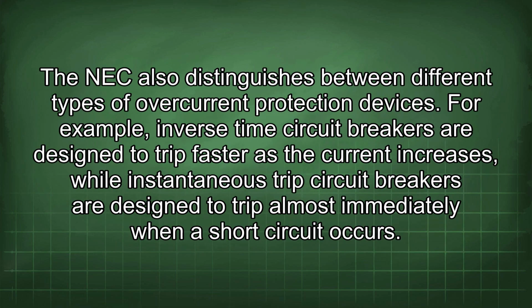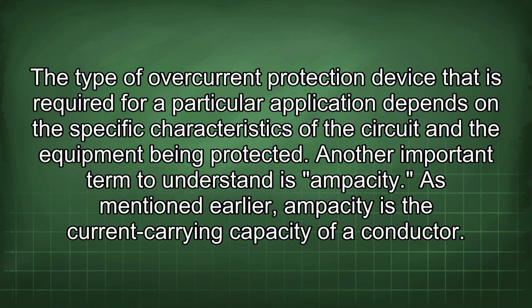The NEC also distinguishes between different types of overcurrent protection devices. For example, inverse-time circuit breakers are designed to trip faster as the current increases, while instantaneous trip circuit breakers are designed to trip almost immediately when a short circuit occurs. The type of overcurrent protection device that is required for a particular application depends on the specific characteristics of the circuit and the equipment being protected.